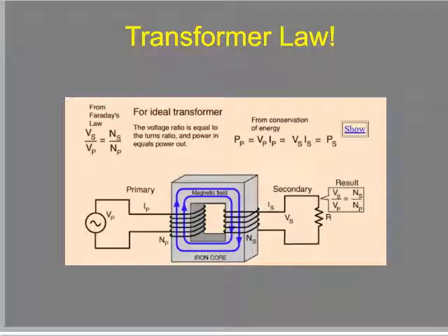Then with the mAs, we have what? Milliamperage. So we're stepping down the current with a step-down transformer, right? Because we do not need all that many X-rays to be produced. We need a specified amount, and it's actually fairly small because an amp is 6.3 times 10 to the 18 electrons per second, and we said that's like a gigazillion.